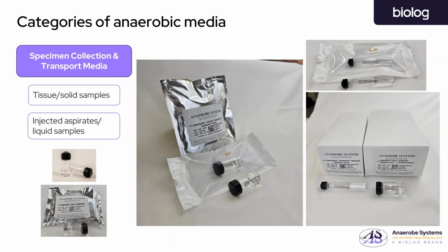And so our standard tubes have a septum Hungate cap on the top, so you can inject directly in. You can also remove the top if you need to, because we have special components in to counter the harmful effects of the media. And speaking of the chemistry and the composition, the transport media is really specifically designed to prevent samples from growing and metabolizing.